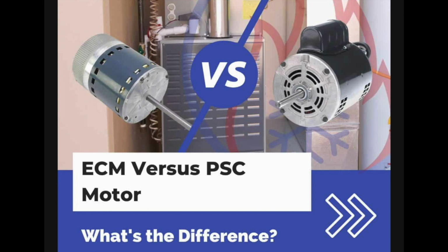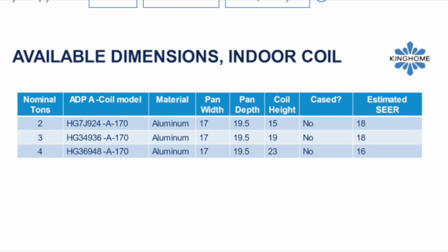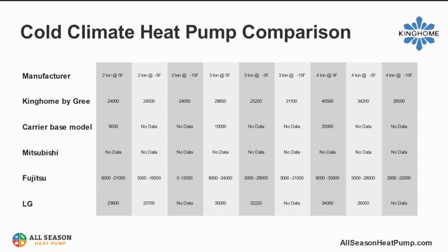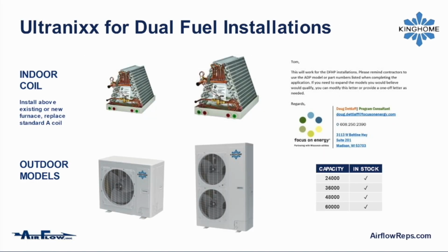Number four, make sure you maximize the efficiency of the coil in order to comply with the rebate requirements. You can't put a teeny little heat pump coil over your furnace and expect the unit to perform similar to catalog data. And finally, number five, if you're using a heat pump other than King Home, make sure you look at the cold climate rebate requirements. Very few heat pumps comply with this standard, and that'll cut your rebate significantly.